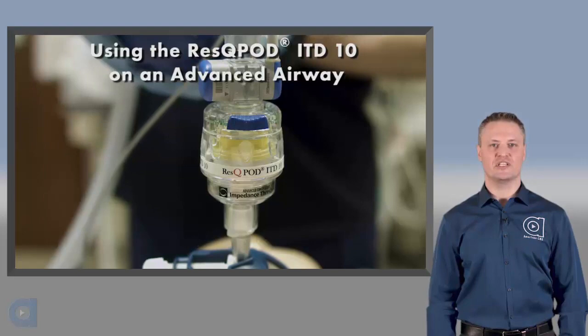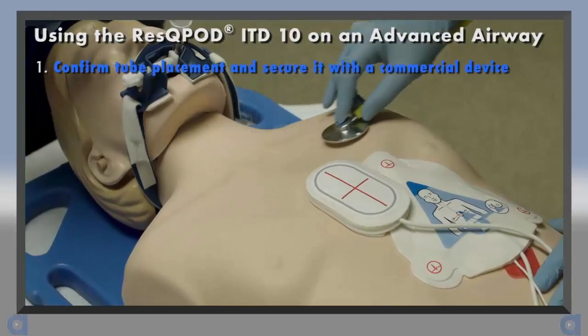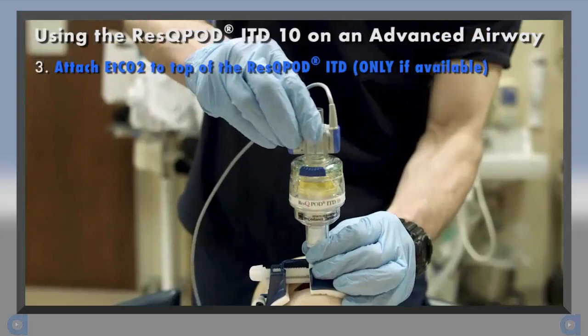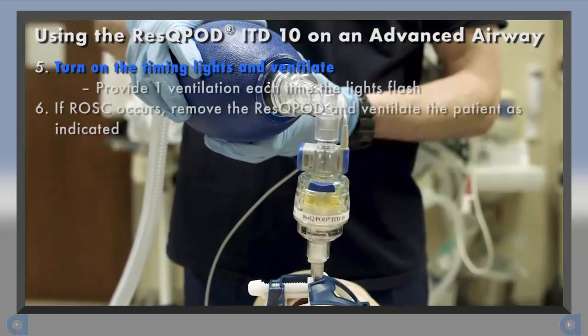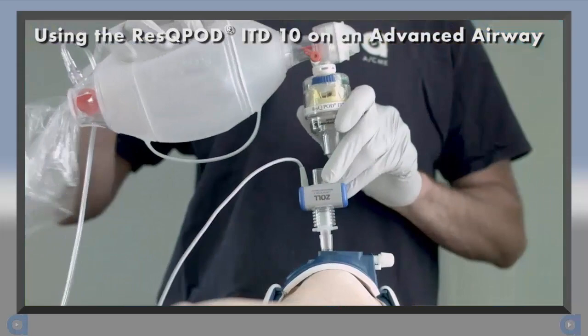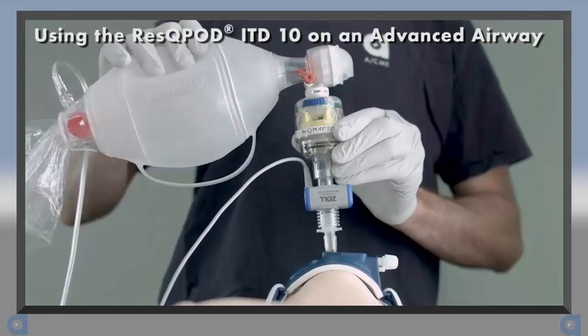Now let's discuss how to use the ResQPOD ITD on an advanced airway, such as an ET tube or supraglottic airway device. Once an advanced airway has been placed, confirm tube placement and secure it using a commercial tube restraint. Then attach the ResQPOD to the airway device. Next, apply an end-tidal CO2 detector if available. After that, attach the BVM. Now turn on the timing assist lights and provide continuous CPR at a rate of 100 to 120 compressions per minute. Each time the lights flash, provide one ventilation. Ventilate over one second and with only enough tidal volume to achieve visible chest rise. If the ResQPOD fills with secretions, remove it from the circuit and use the ventilation source to clear it.